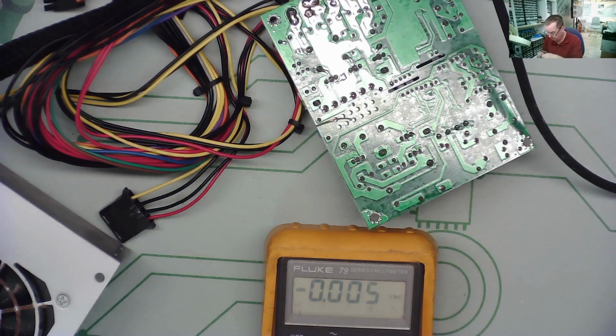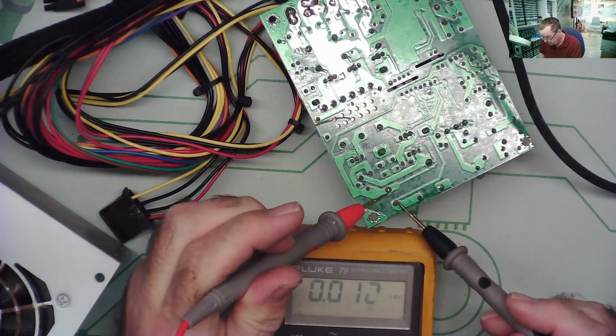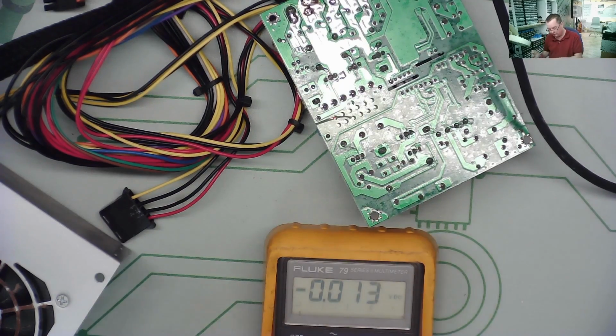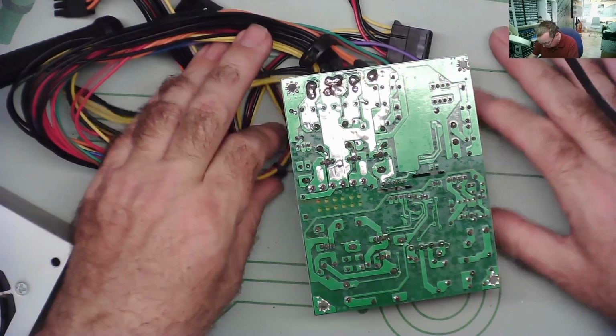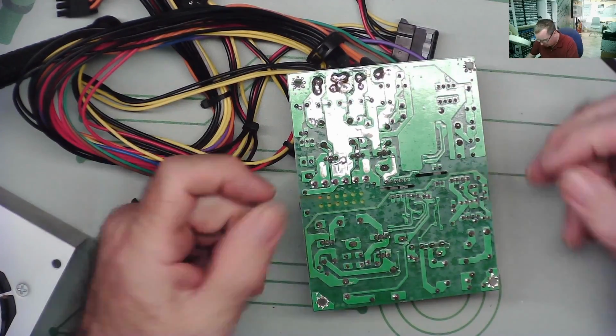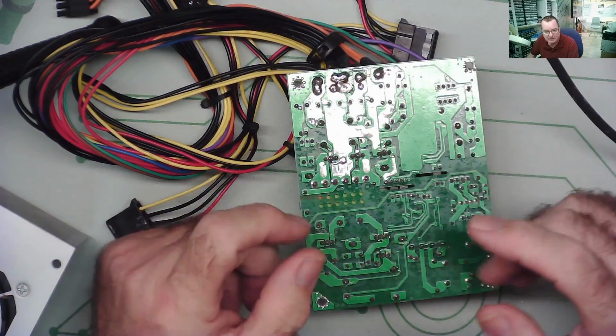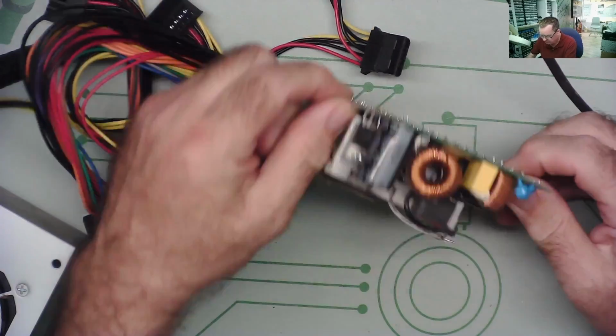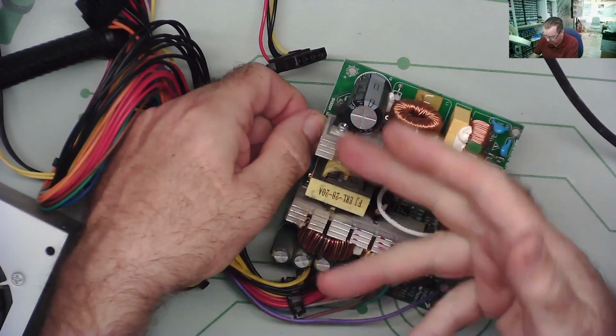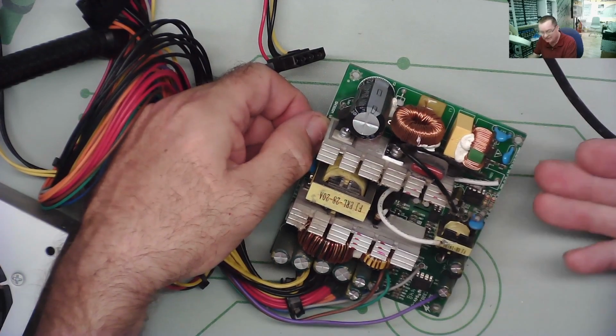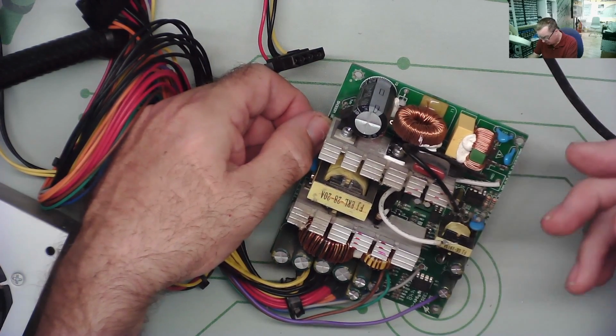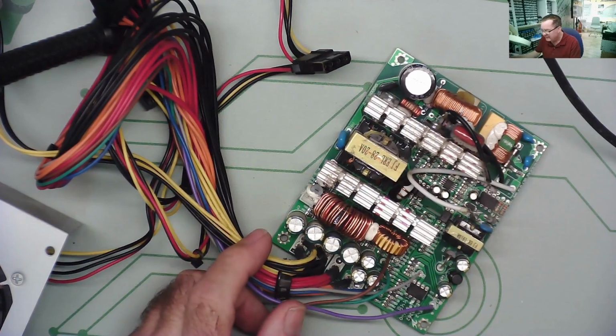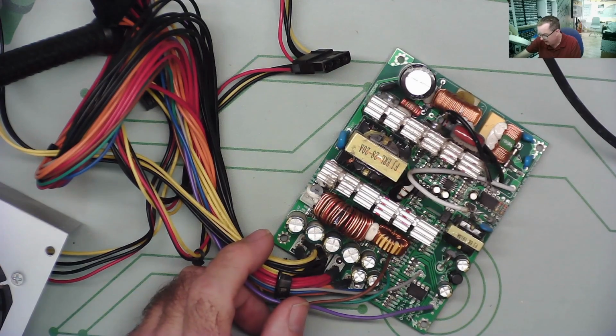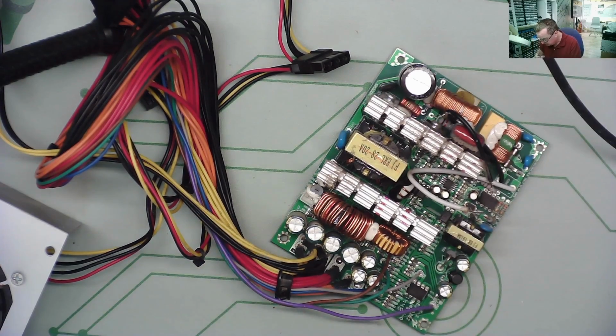There, the voltage is gone. So we can work on this now. The fact that we had a high voltage in the main capacitor and it wasn't discharging tells me that the main power supply, and for that matter the standby power supply, are not running. But we really knew that anyway because of the fact we had no standby voltage.